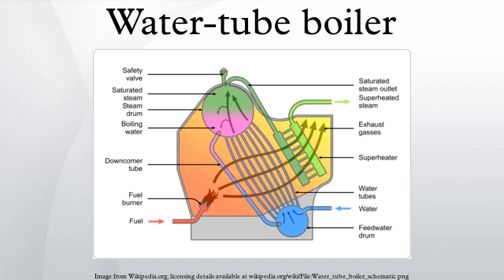The Stirling boiler has near-vertical, almost straight water tubes that zigzag between a number of steam and water drums. Usually there are three banks of tubes in a four-drum layout, but certain applications use variations designed with a different number of drums and banks. They are mainly used as stationary boilers, owing to their large size, although the large grate area does also encourage their ability to burn a wide range of fuels.